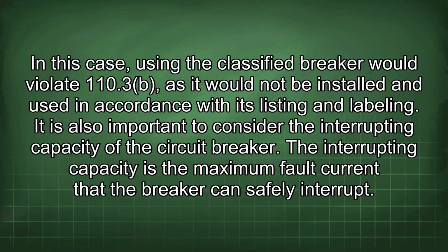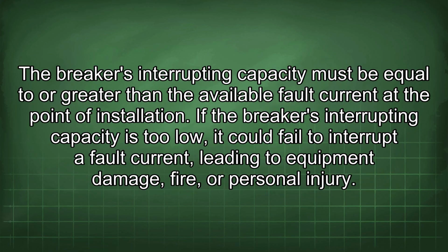It is also important to consider the interrupting capacity of the circuit breaker. The interrupting capacity is the maximum fault current that the breaker can safely interrupt. The breaker's interrupting capacity must be equal to or greater than the available fault current at the point of installation.